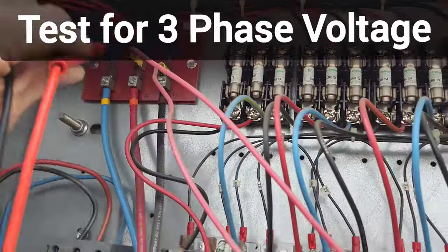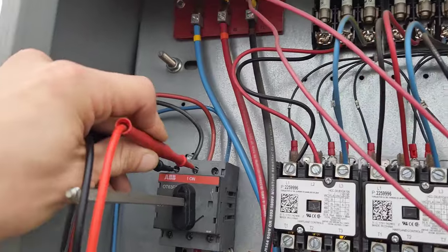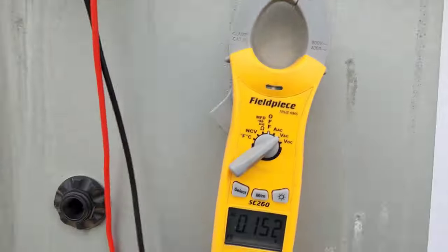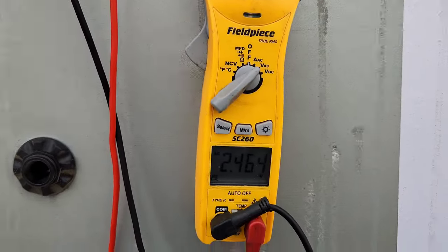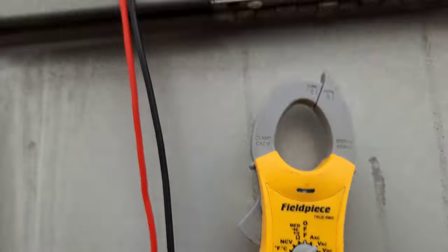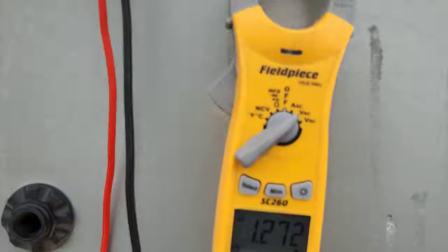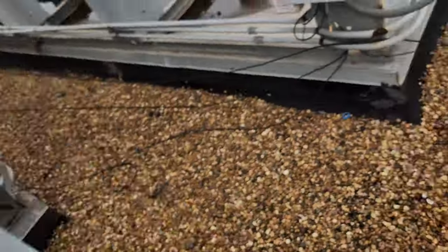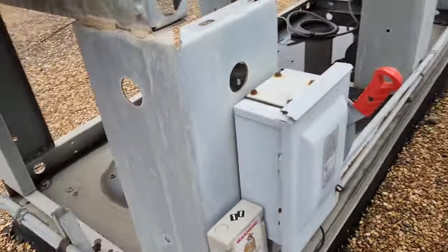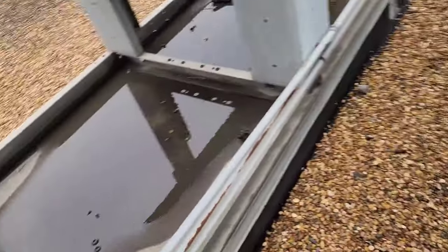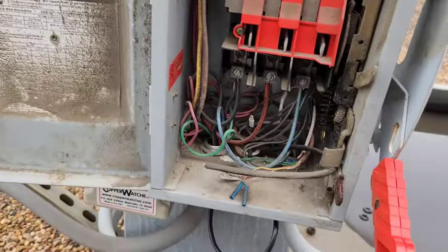So on the roof, I found nothing running. So I start by checking my power. I like to go phase to phase and then each phase to ground. And I find no power coming into it. So we've got a disconnect up there. I want to make sure that the disconnect doesn't have any fuses in it, and this one doesn't.